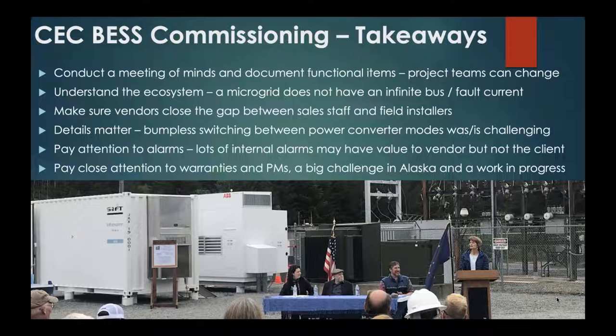We want those control signals to be absolutely robust, and we don't want a $30 or $40 switch or modem to fail. So we had serial connections for our communications commands, and used Modbus TCP/IP for all the alarms and general data flow that weren't as critical. That was an architecture that kind of got lost in translation, and we had to quickly order and replace one.